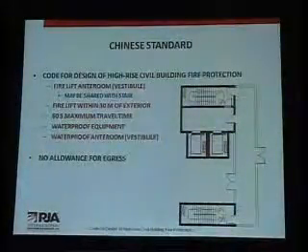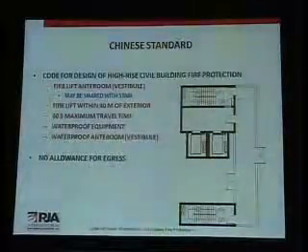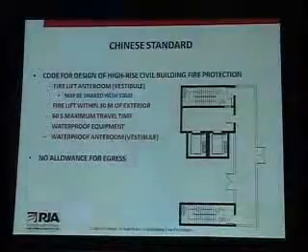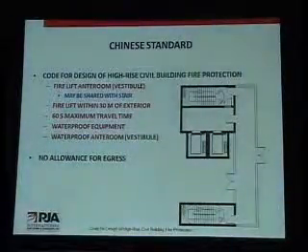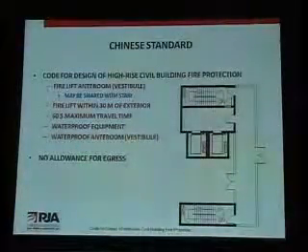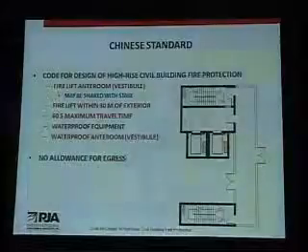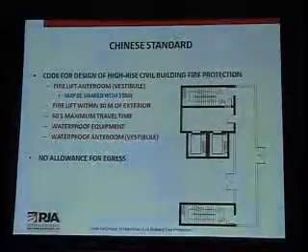So we're going over into the Chinese standard, and Jim had mentioned that there are some similarities with the European Union standards. But if you look at the configuration, they do require a vestibule for the elevators. However, the vestibule is not required to be shared with the stair. It can be, but it's not required.